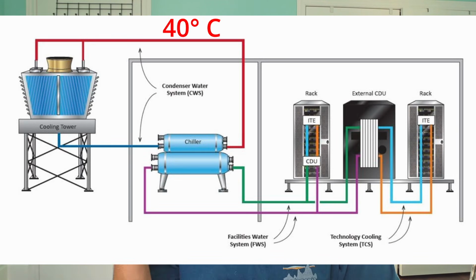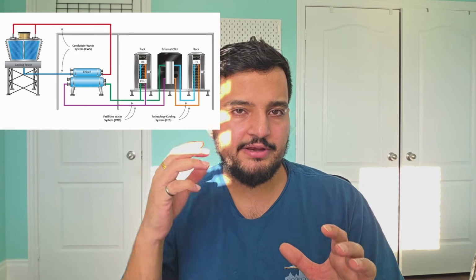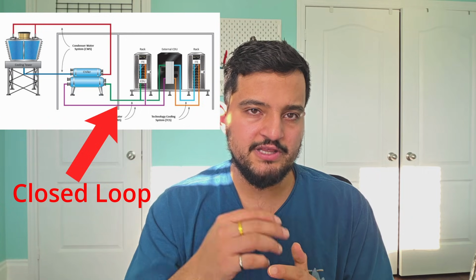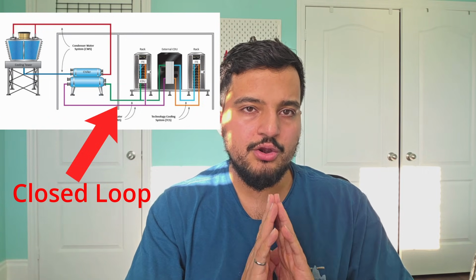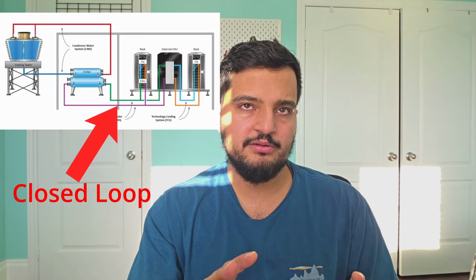So it's going to cool that chilled water, and on the other side, it's going to heat up a different medium. On the condenser side of the chiller, you have a set of pumps that circulates more water to collect that heat from the chilled water and is heated to something like 40 degrees Celsius as this heat is collected. Although this depends on the particular design of the system. So here's where the water use comes in. So far, we've talked about closed loop water circulation inside of the data center. So inside of the building, the water is circulated in a continuous closed loop in the form of chilled water. So therefore, no water is actually lost from inside of the building.